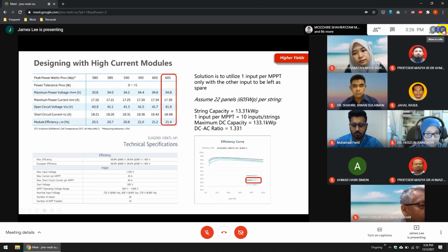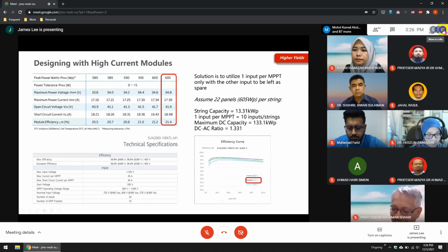If you were to use all the inputs per MPPT, so 2, that means 20 inputs, you're going to have a DC-AC ratio which is quite ginormous. It may not be practical, and I don't think it's worth your investment to throw money into DC when your AC is capped already. So in this case, all you need to do is fill up one input per MPPT, so you've got 10 MPPTs, 10 strings, and your DC-AC ratio is already reaching 1.33.